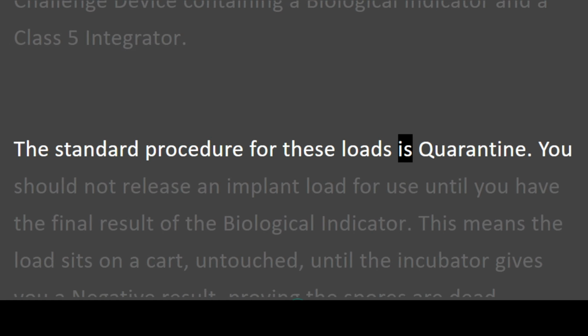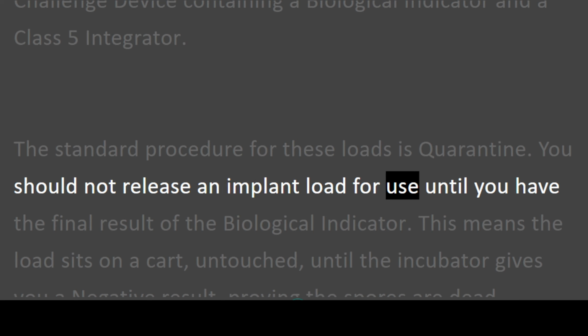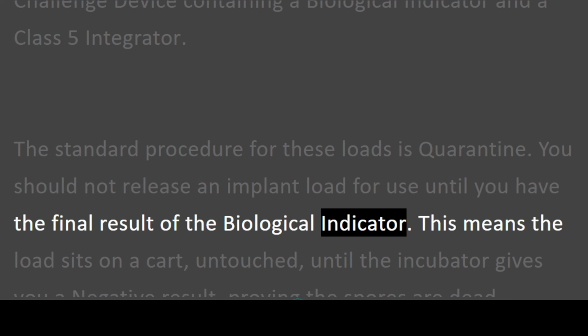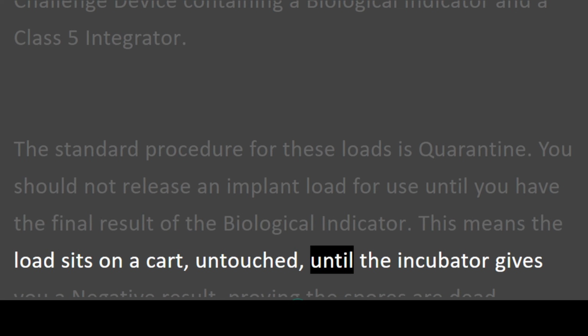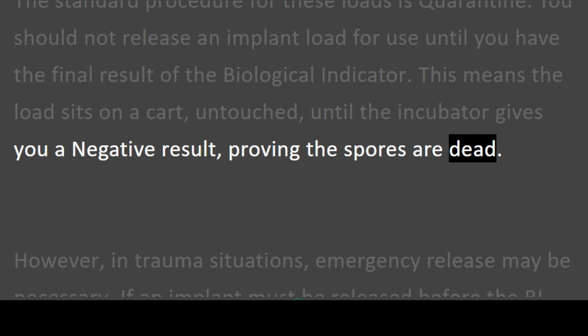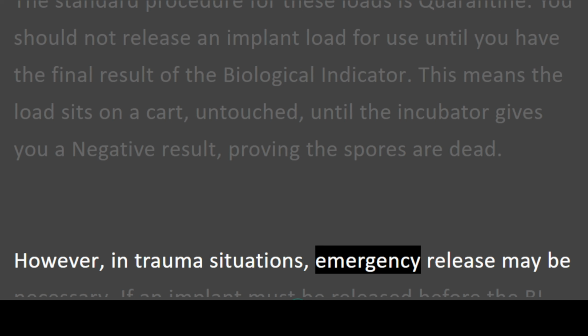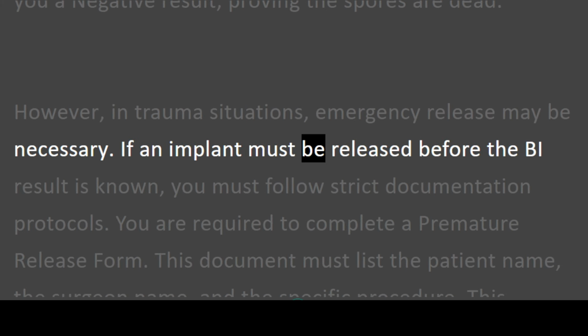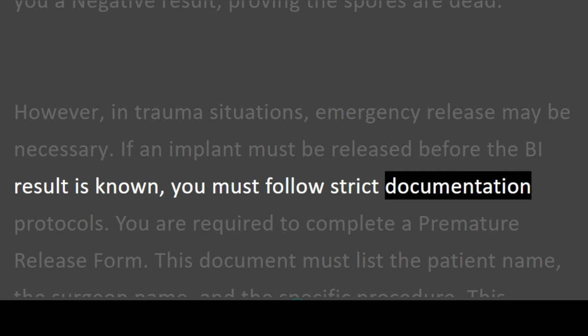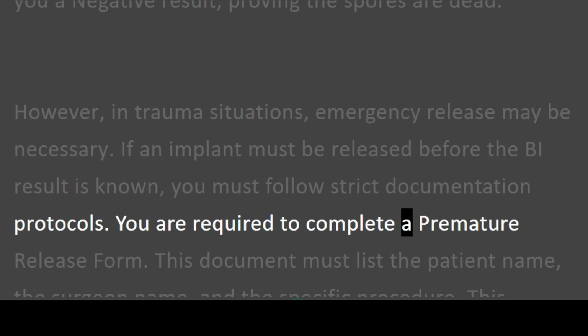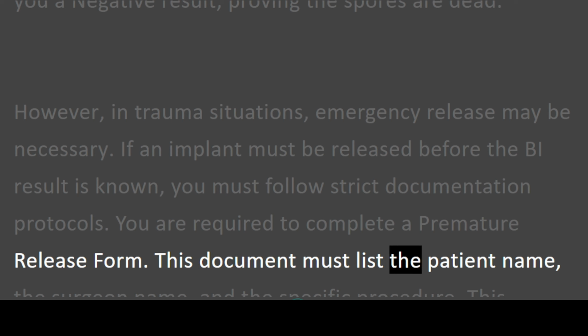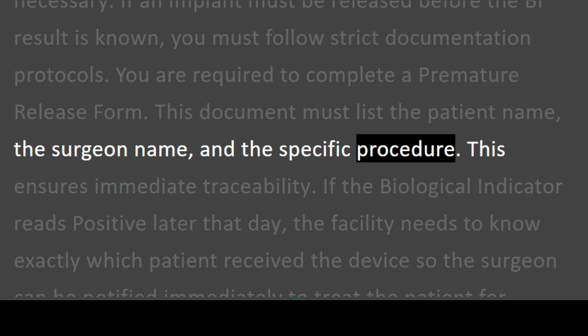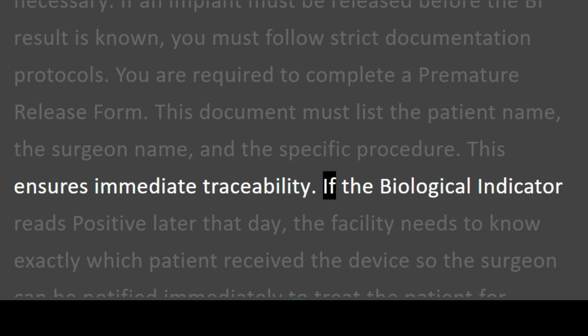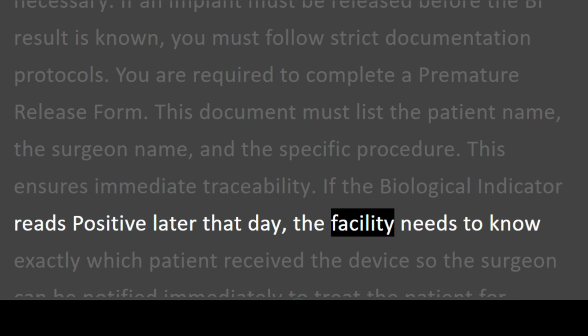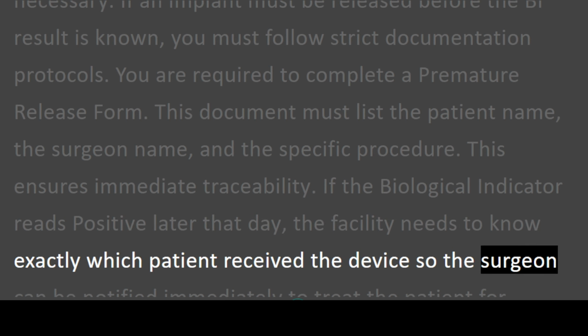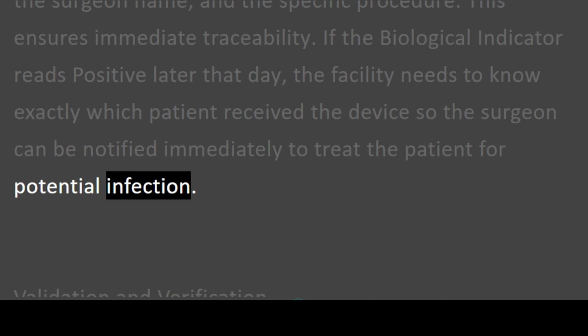The standard procedure for these loads is quarantine. You should not release an implant load for use until you have the final result of the biological indicator. This means the load sits on a cart, untouched, until the incubator gives you a negative result, proving the spores are dead. However, in trauma situations, emergency release may be necessary. If an implant must be released before the BI result is known, you must follow strict documentation protocols. You are required to complete a premature release form. This document must list the patient name, the surgeon name, and the specific procedure. This ensures immediate traceability. If the biological indicator reads positive later that day, the facility needs to know exactly which patient received the device so the surgeon can be notified immediately to treat the patient for potential infection.